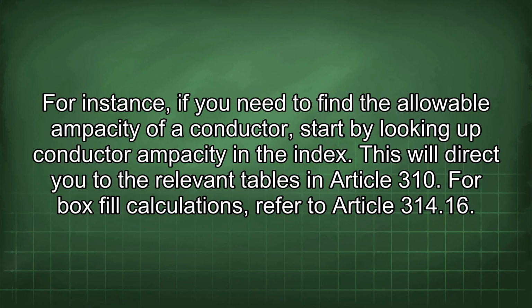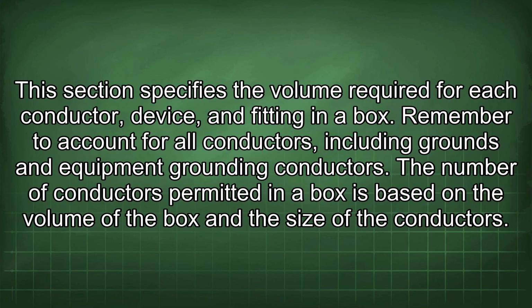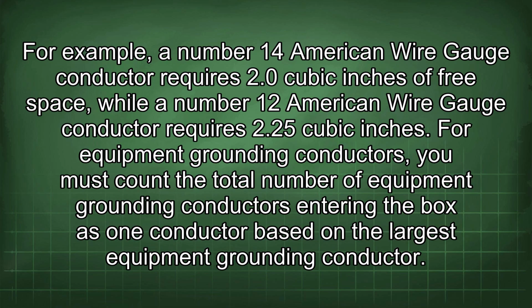For box fill calculations, refer to Article 314.16. This section specifies the volume required for each conductor, device, and fitting in a box. Remember to account for all conductors, including grounds and equipment grounding conductors. The number of conductors permitted in a box is based on the volume of the box and the size of the conductors. For example, a number 14 American wire gauge conductor requires 2.0 cubic inches of free space, while a number 12 American wire gauge conductor requires 2.25 cubic inches.